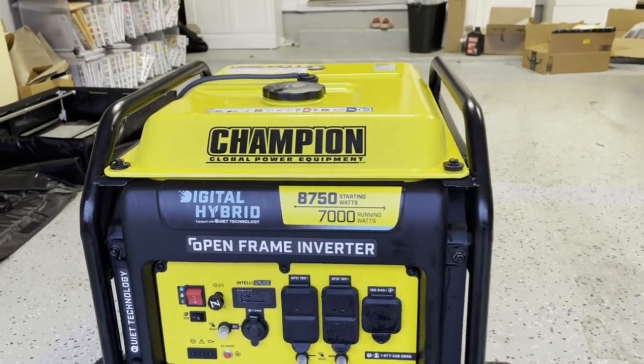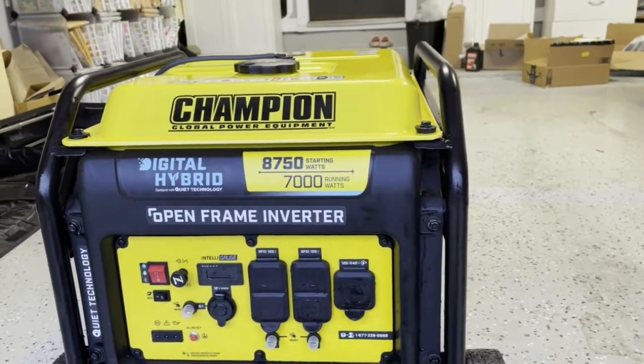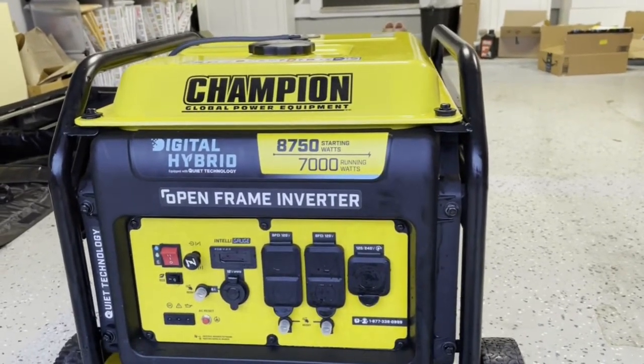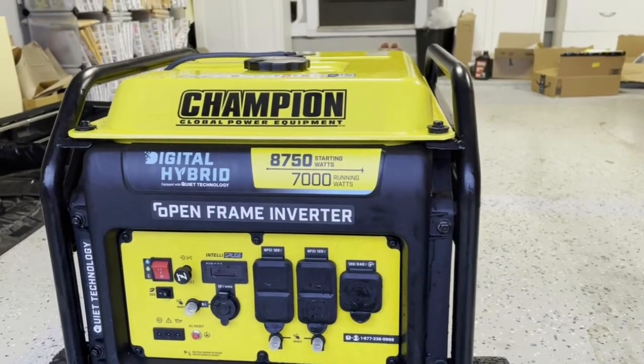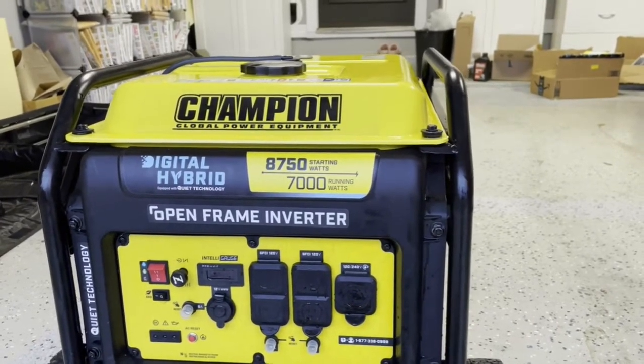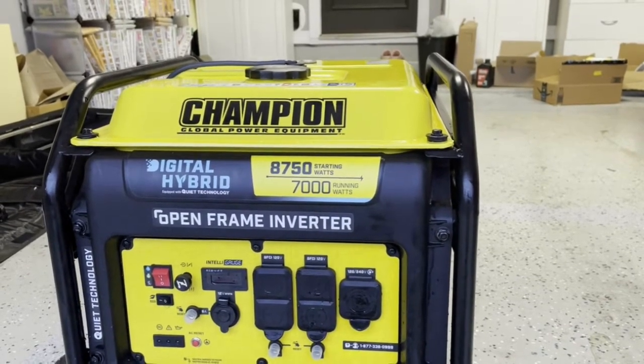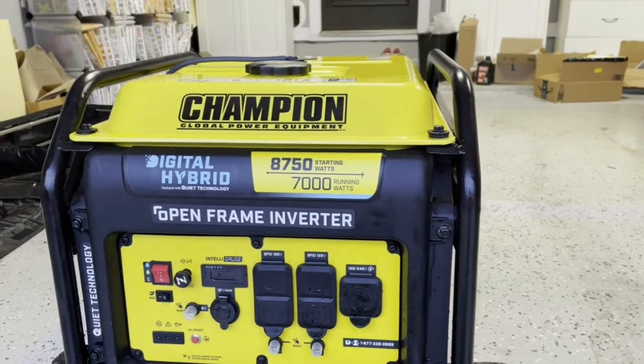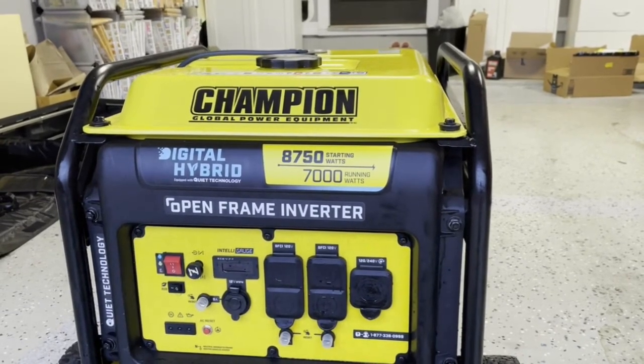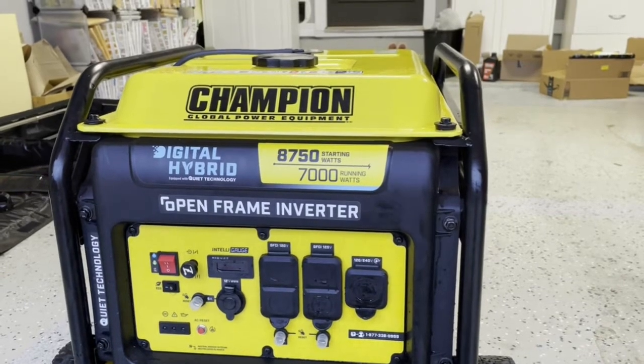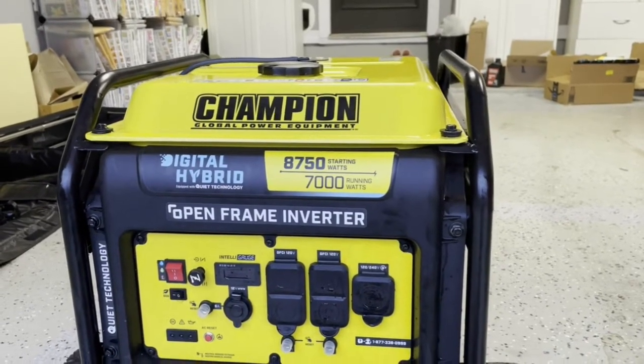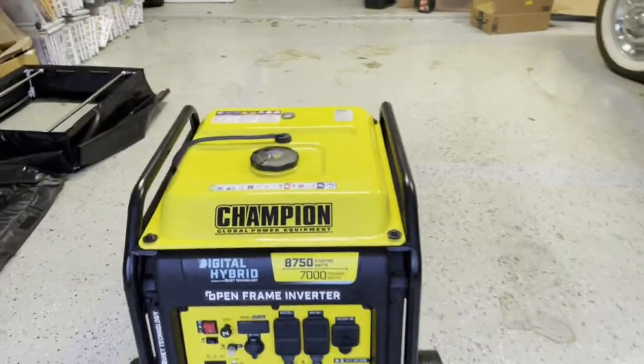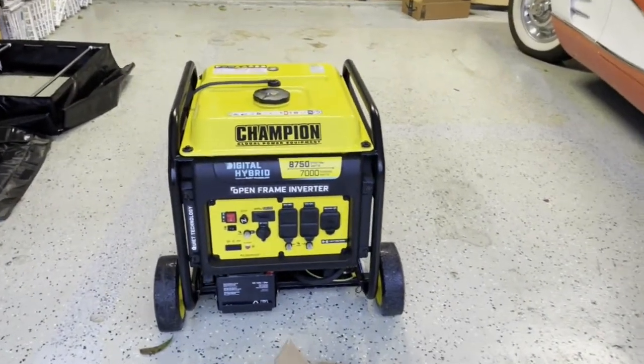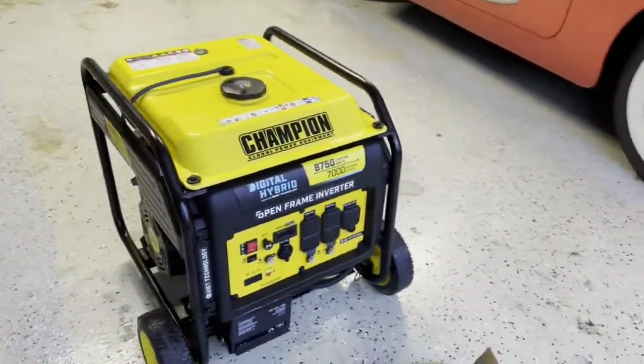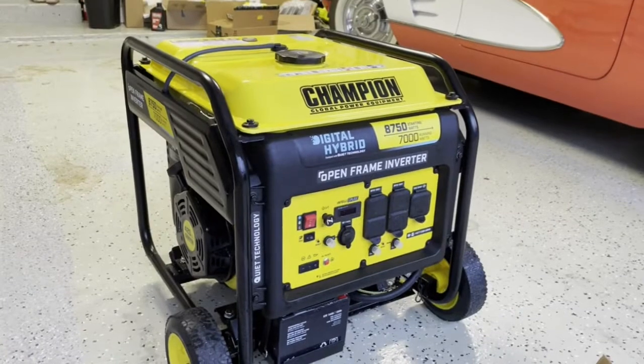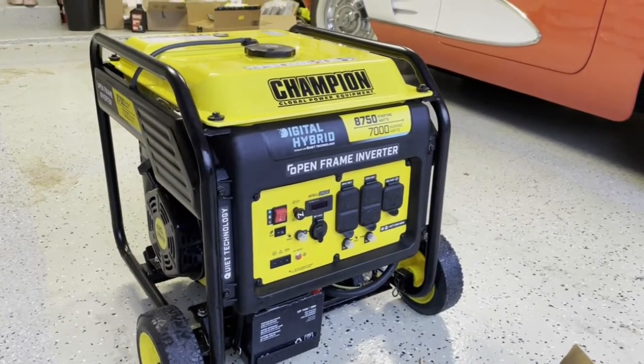If you don't want that to happen, there are fuel stabilizers you can add so the fuel can last up to a year, but that's still limited. You need to drain or choke your carburetor by shutting the gasoline valve before stopping the generator, and store it properly. Meanwhile, natural gas is a continuous source of energy, so it's always a good idea to run on natural gas instead of gasoline, or at least have it as a backup option for continuous operation.